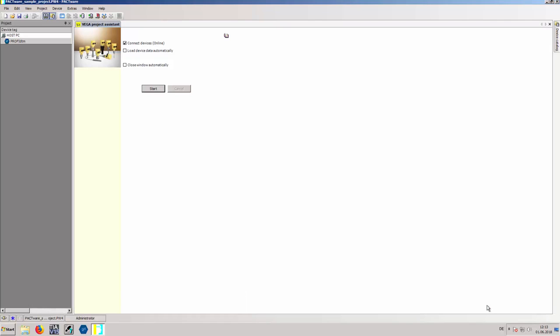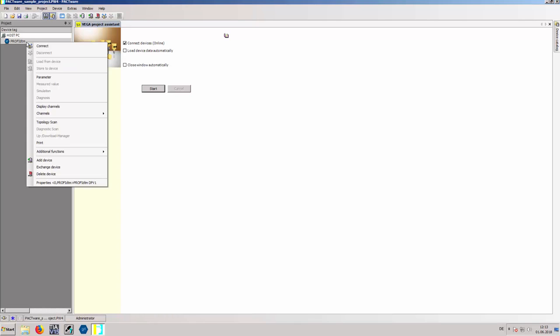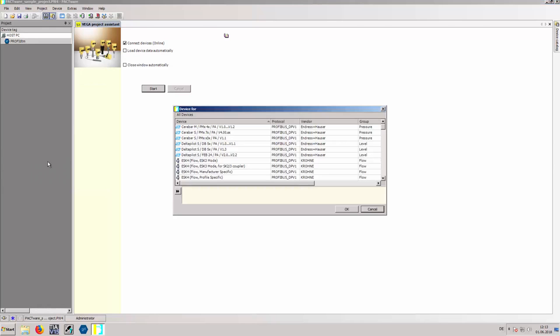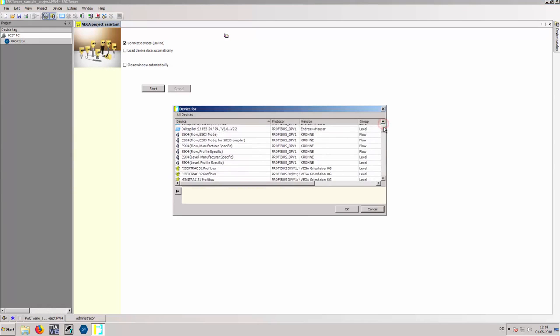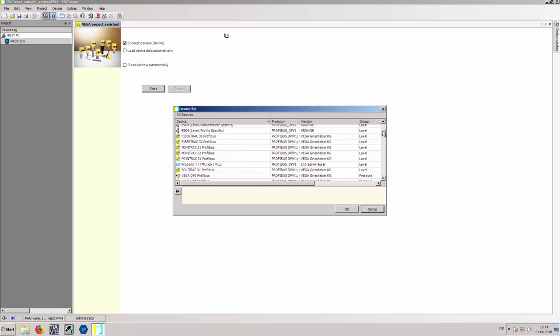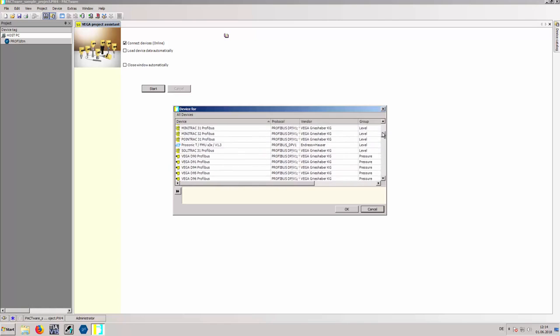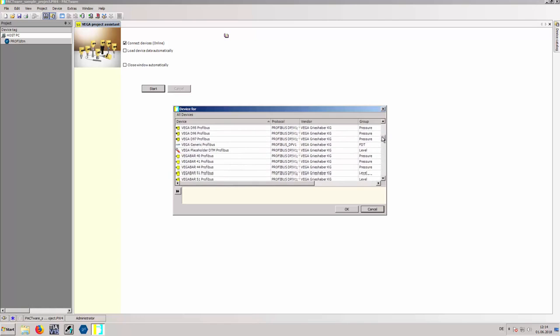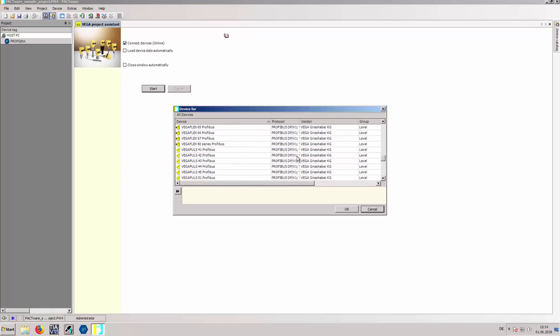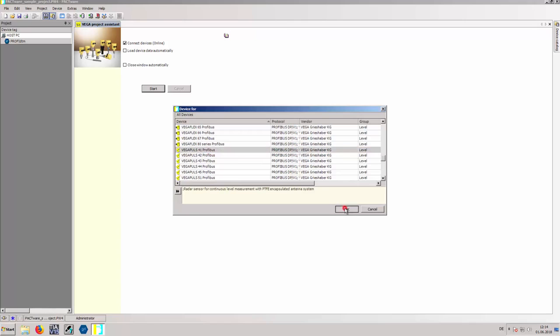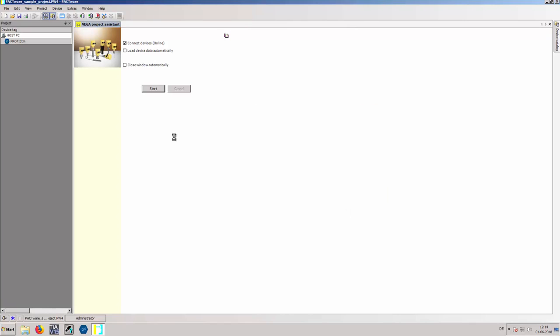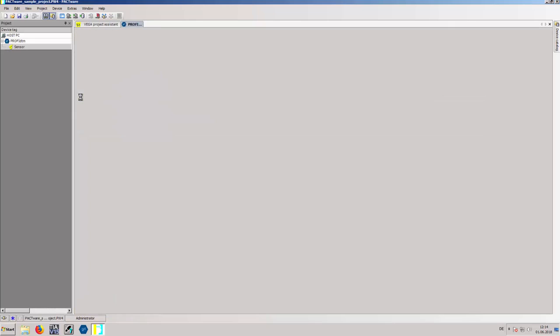Add a new device using a right-click on ProfiDTM and Add Device. Find the actual PA device in the list, select it and confirm with OK. Enter the Profibus PA device address and confirm with OK.